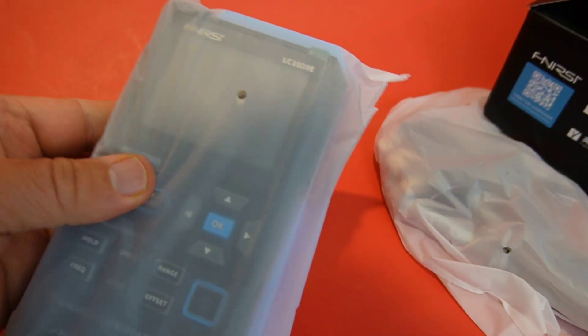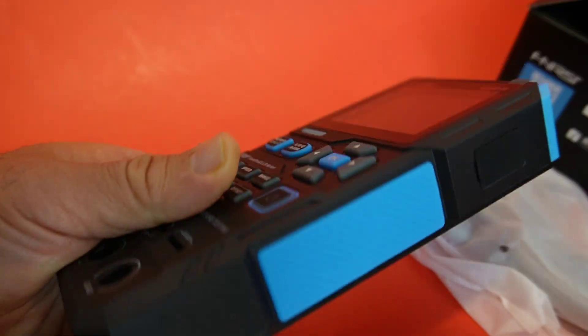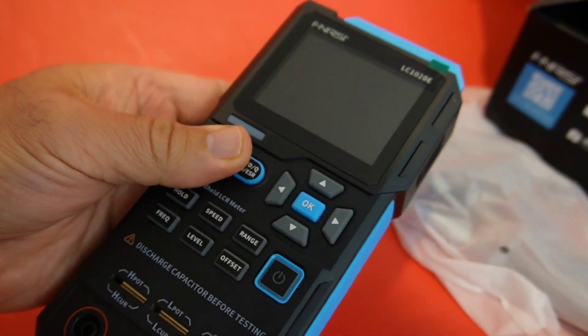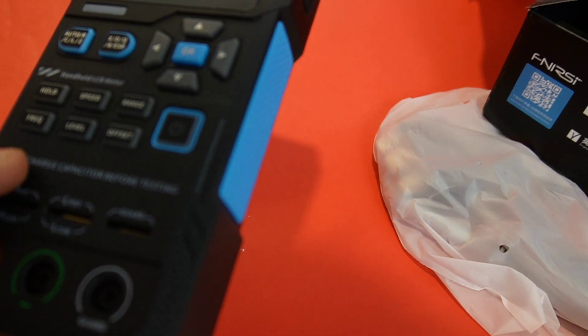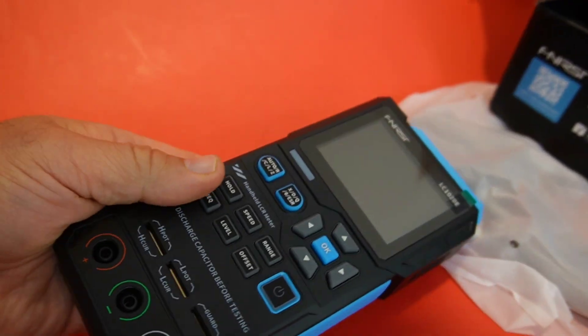Let's start off with the meter itself. Take it out of this really nice protective wrap. It has some good weight to it — right at the get-go, this is a hefty little guy. Nice rubber inlay here on the side. That FNIRSI blue, which I really like. It's generally a good-looking test instrument. All the buttons here are rubberized, and of course we have our plates down here — the high pot, the low pot, the guard, positive, negative, and another guard input.